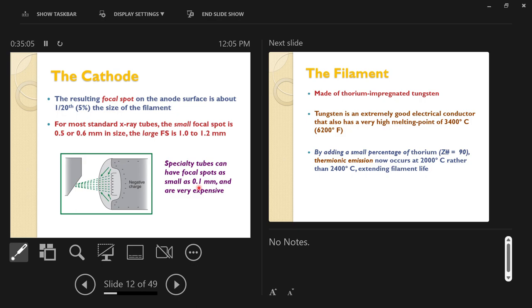The room with all the lights on is brighter than one flashlight — that's the advantage of a large focal spot for x-ray production. Large focal spots can produce more x-rays; small focal spots produce relatively fewer x-rays but give added image detail. You have to choose: improved detail or better x-ray producing capacity. You can't have both, though in the middle there's some gray area.